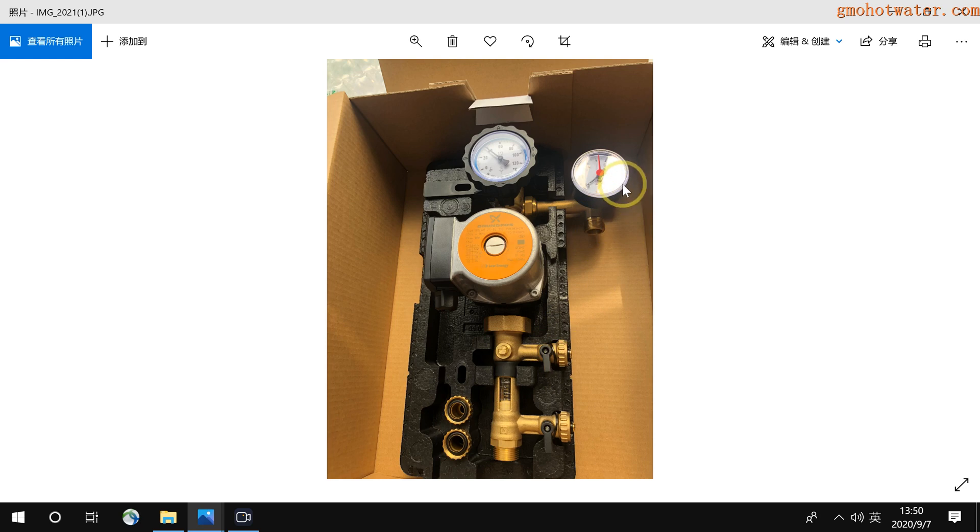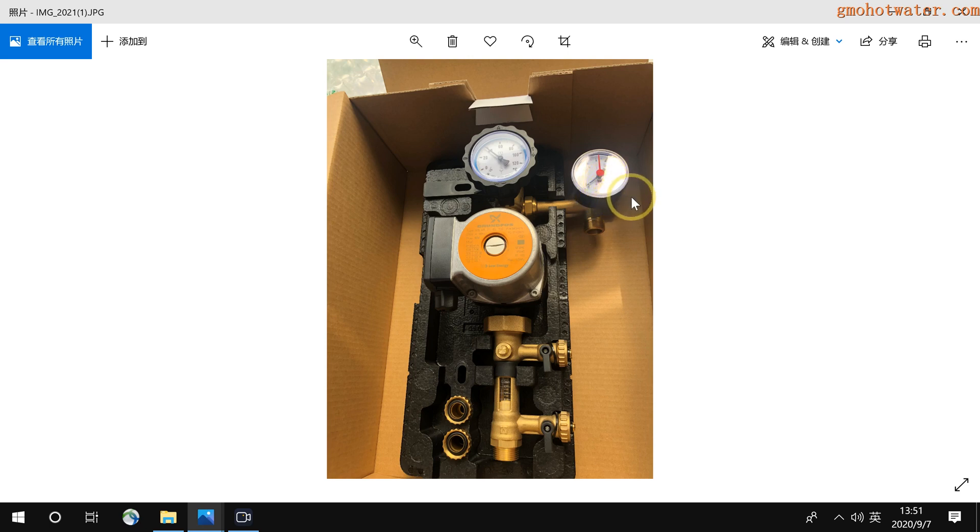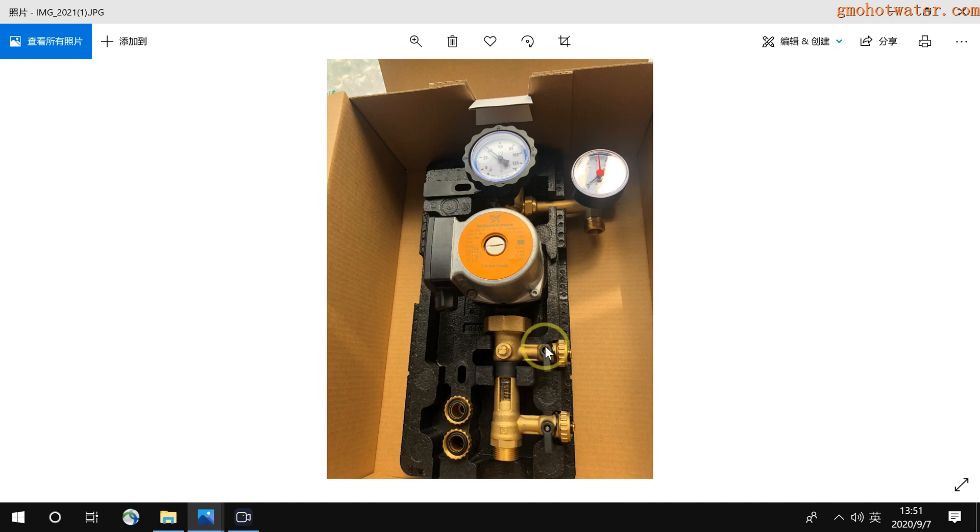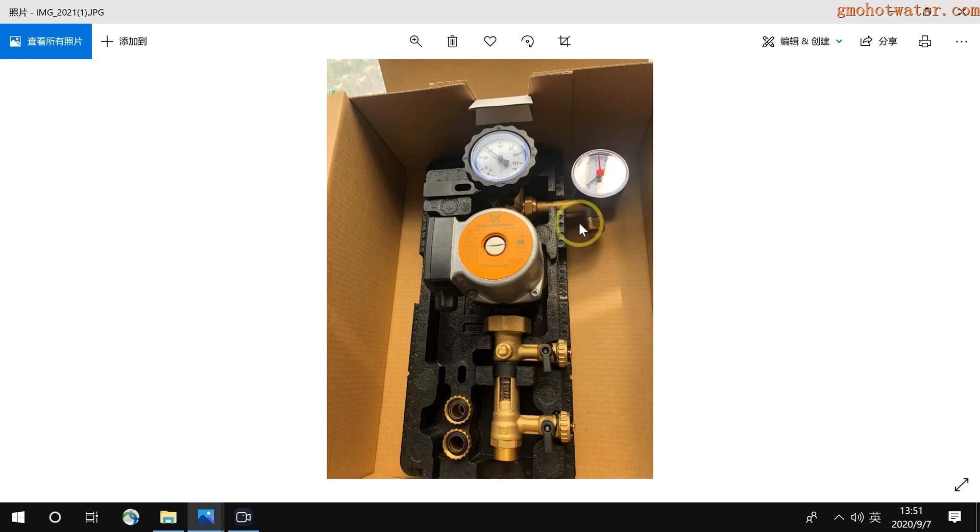And at the back here is a pressure valve. When it reaches 6 bar, it will open and drain the water from here. These two valves are used for injecting the heat transfer liquid. Because we are using water circulation, we don't use it anymore. And these two connections are sealed by the valve. So we can borrow one plug from here and block the connection for the expansion tank.